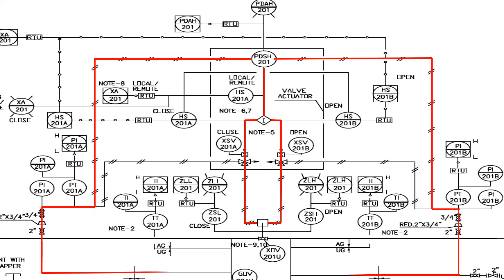When we closely watch the differential pressure switch, we can see that two pneumatic lines are connected to it. The differential pressure between the upstream and downstream of the XDV valve is used to activate the interlock, which determines whether to open or close the XDV valve.